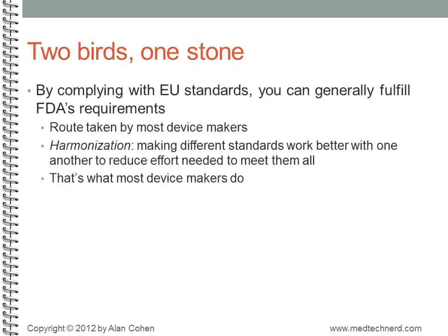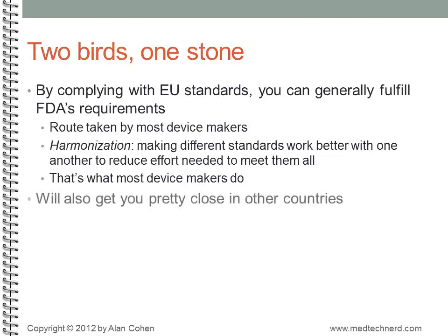The good news is that governments and standards bodies around the world have worked together to make their standards more compatible with one another. This process is known as harmonization. Currently, the strategy employed by most device makers is to comply with the EU CE mark standards, which will typically essentially fulfill FDA's requirements. The EU CE mark standards will also get you pretty close to where you need to be in other markets as well. So in this presentation, we'll be focusing on standards that are needed in the EU. This will get most devices most of the way to where they need to be.